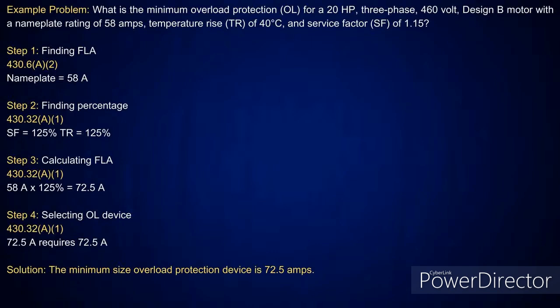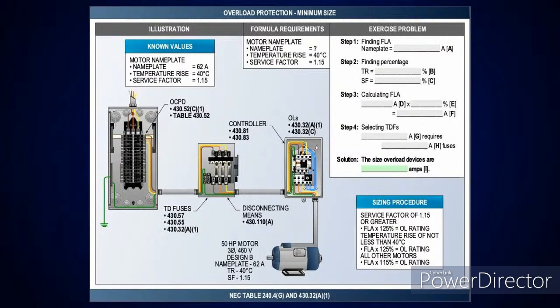And you want to look at 430.32(A)(1), and you'll see they're listed out right below the text, with three of them there with the percentages. So if I'm at 125% for my service factor and temperature rise, I'll take that at 125%, and that'll give me 72.5 amps for my motor overload protection. And then you'll see we have it set up here, with a nameplate value of 62 amps, 40 degrees C and 1.15. I know that's 125%.